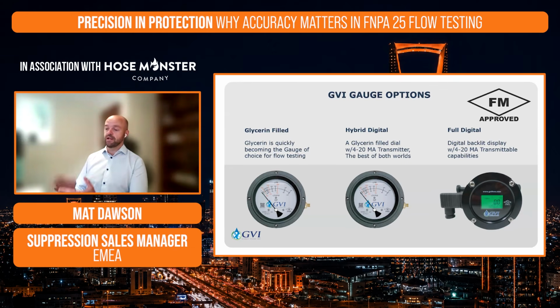So when we talk about the accuracy, what we're doing here is we're testing fire pumps, and there's a potential that if we get a wrong reading, we might fail a fire pump. So we need to make sure that the readings we're getting are 1, accurate, and 2, read correctly. So the first solution we have for that is our glycerin filled dial. Glycerin's basically a clear syrup. And what we're looking to do with the glycerin is take away the needle bounce. So we're looking for a cost-effective, accurate gauge that can be read really easily. Again, we're really proud to say that this is the only FM-approved glycerin-filled dial on the market, and that's why we're seeing a big uptake of it.